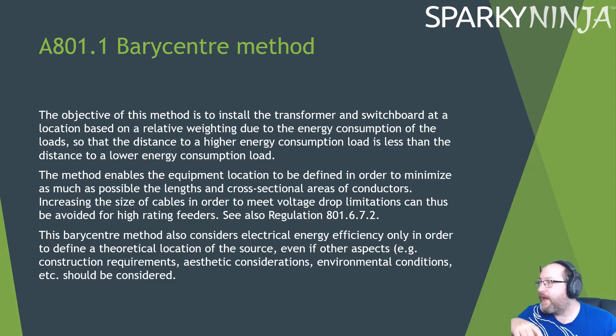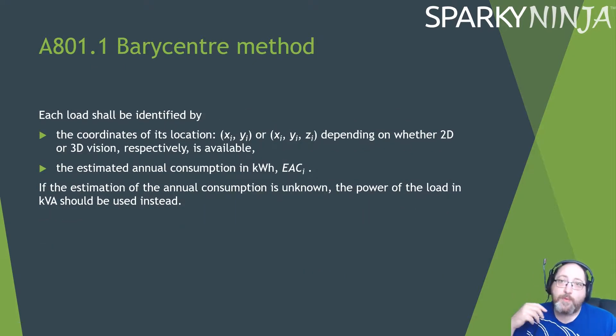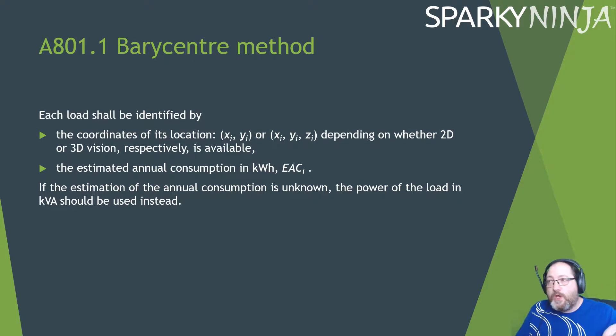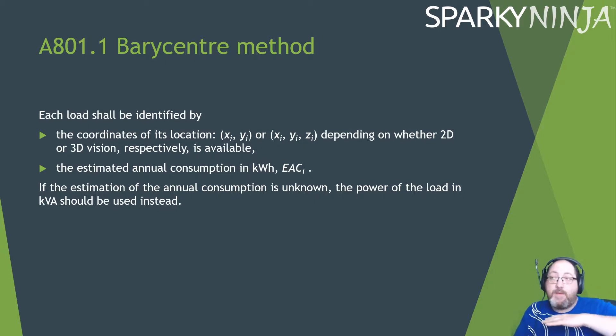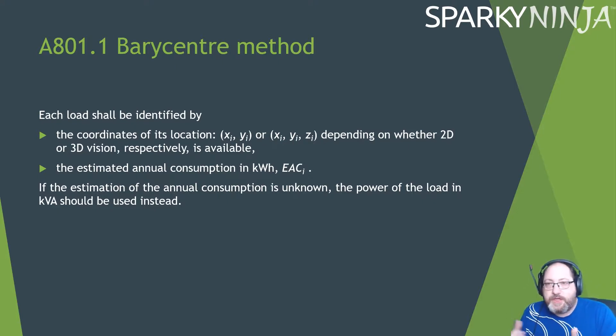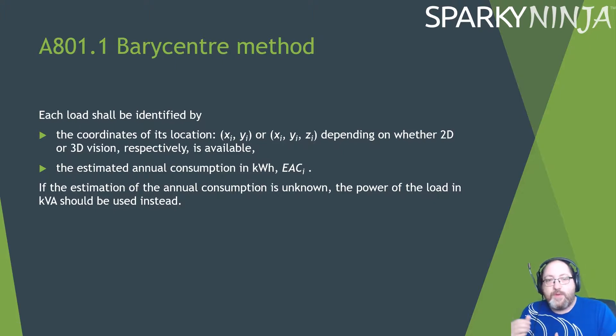Each load will be identified by the coordinates of its location. You go to the customer and find out what they have and where it's going. Depending on whether you're on a single floor or multiple floors, you'd do either a 2D or 3D calculation. For two dimensions you use X and Y coordinates; for three dimensions you add Z. You'll also need the estimated annual consumption in kilowatt hours — the EAC — for each load.